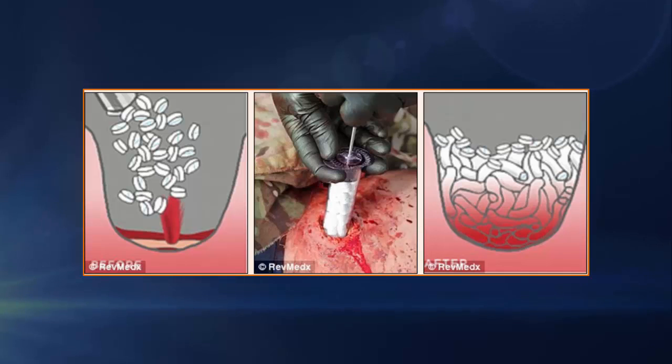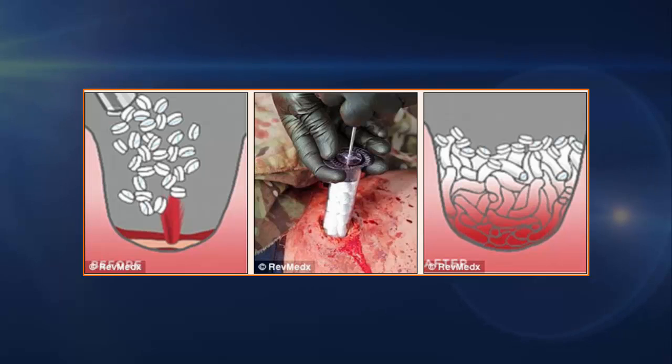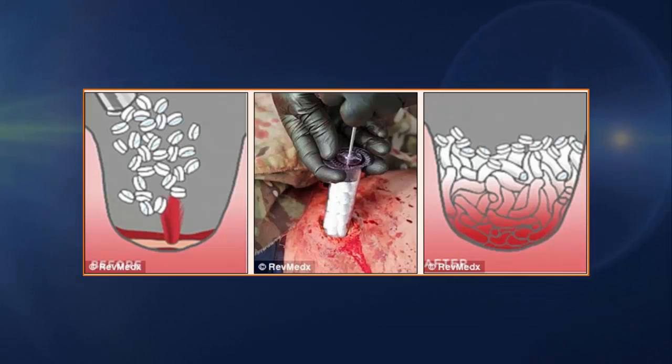This gives emergency responders up to 4 hours of use — a significant amount of time to transport the victim to a hospital. Each sponge is 9.8 mm wide and 4–5 mm tall, with capabilities of absorbing 3 mL of blood or bodily fluid. With 92 sponges packed into each applicator, the X-Stat has the potential to absorb roughly 300 ml of fluid for one victim.